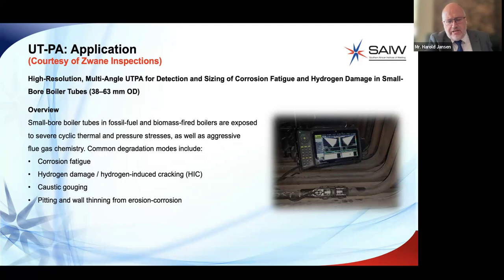Eskom has initiated a considerable effort to optimize boiler tube inspections by transitioning from radiographic testing to small bore phased array ultrasonic inspections while maintaining safety standards. Zwane Inspections is among the organizations that have successfully adopted this advanced inspection technique. There's a brief overview. Small bore boiler tubes in conventional power boilers are exposed to severe cyclic thermal and pressure stresses, as well as aggressive flue gas chemistry. Common degradation modes include corrosion fatigue, hydrogen damage such as hydrogen-induced cracking, caustic gouging, pitting, and wall thinning from erosion and corrosion.